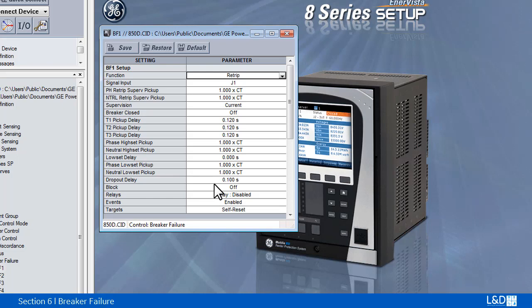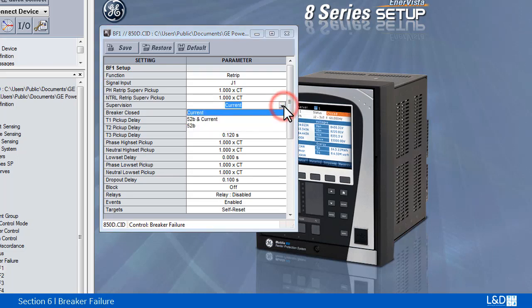This feature is usually described as re-trip. The scheme determines a breaker failure condition supervised by one of three conditions: current, breaker status and current, or breaker status only.